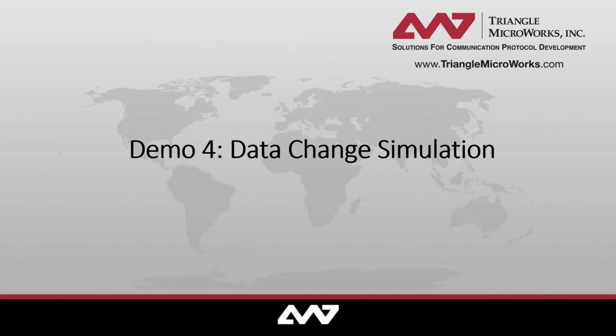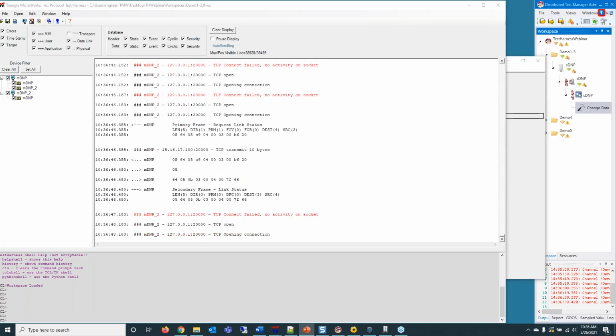So in this scenario, we're given a master device who seems to disconnect at seemingly random times. We've configured our test harness's simulated outstation to match the field outstation as much as possible. Our hope here is to recreate the disconnect and track down why it's timing out. So let's go ahead and look at that.